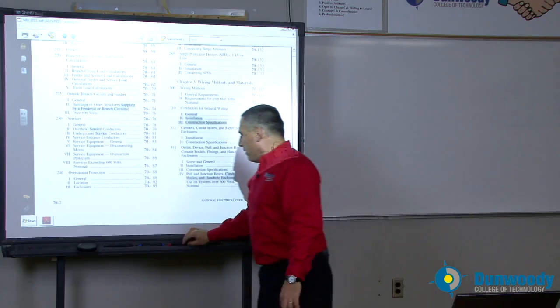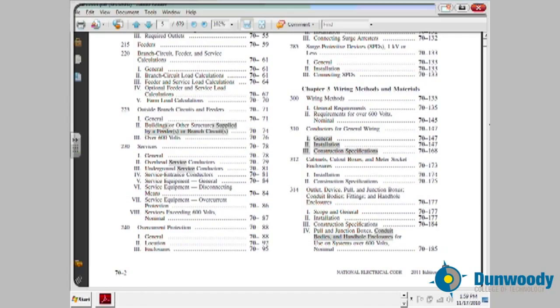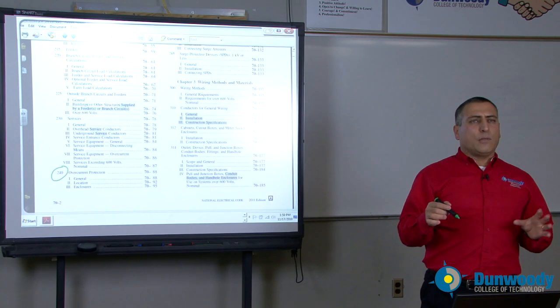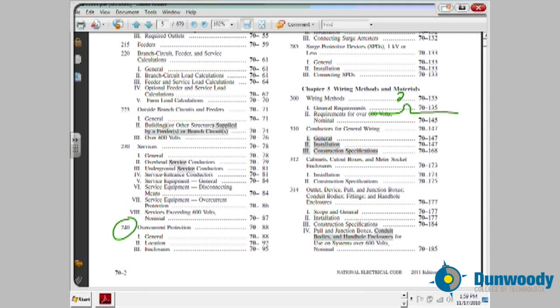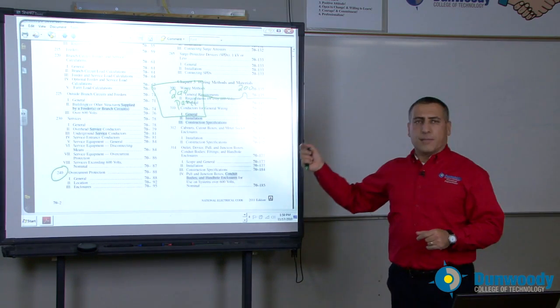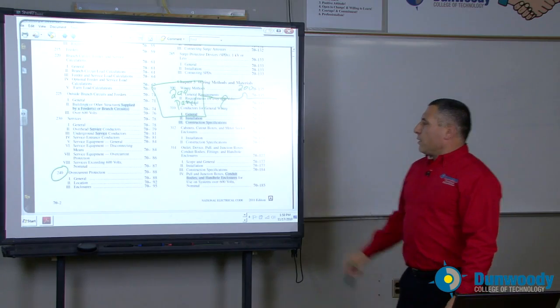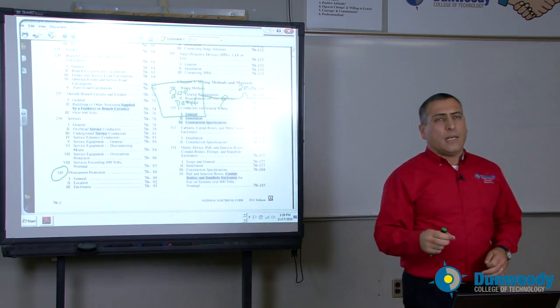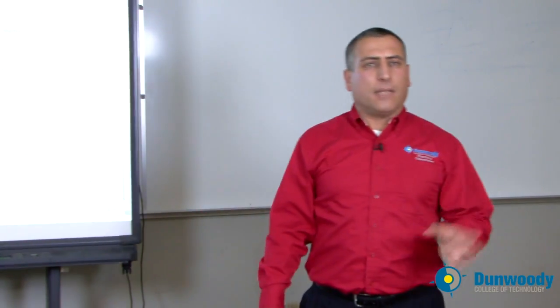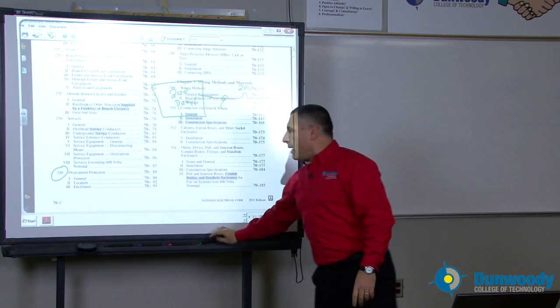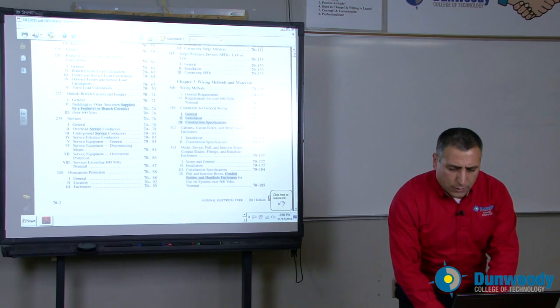Another very important topic is overcurrent protection devices. Every time we have a conductor carrying a load, you need an overcurrent protection device. For example, a 200-amp panel must be protected by a 200-amp circuit breaker, wired through a conductor — whether a feeder, branch circuit, or service. The conductors must have an overcurrent protection device sized correctly to protect the panel as well as the conductors themselves.